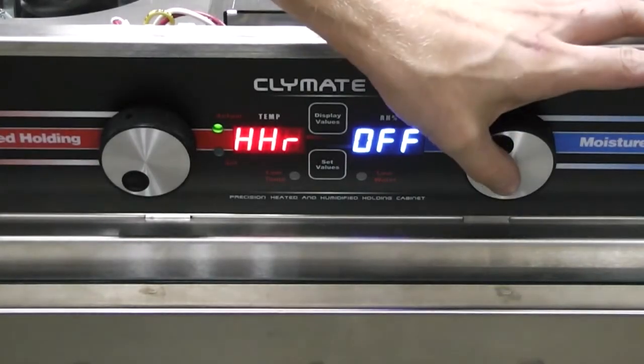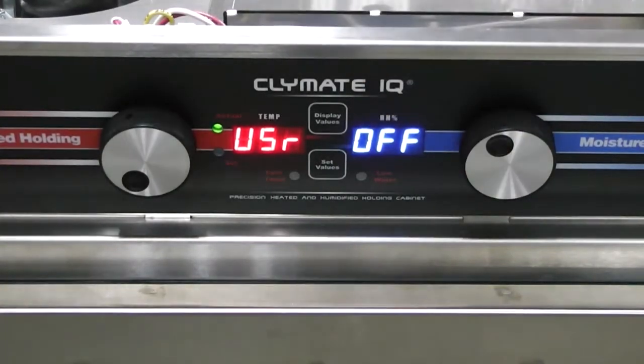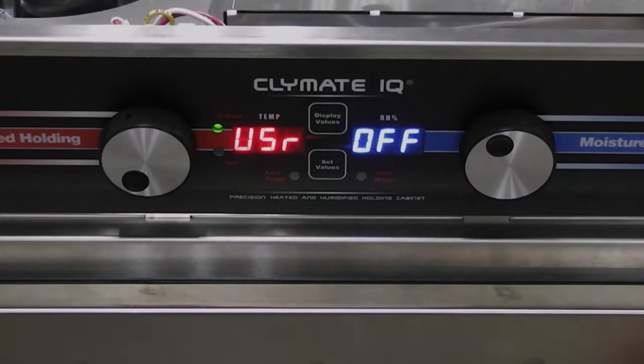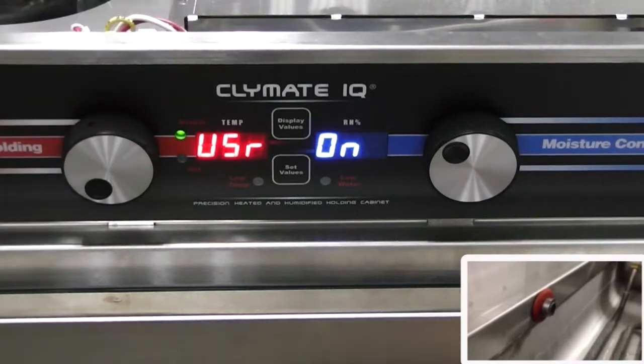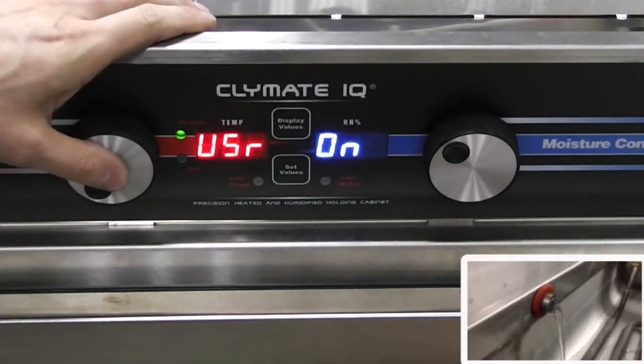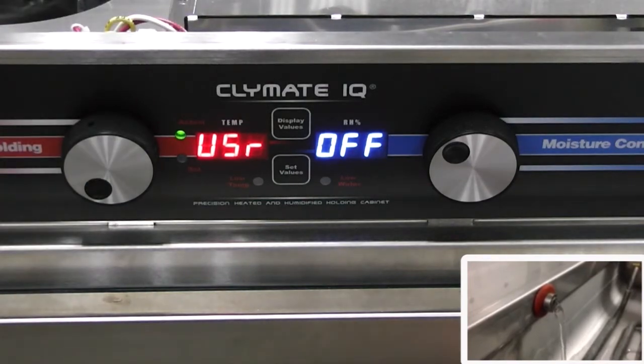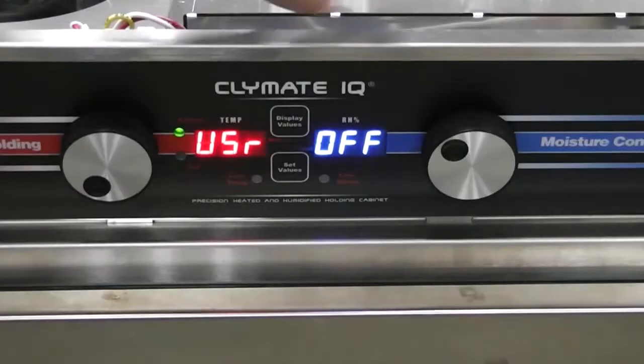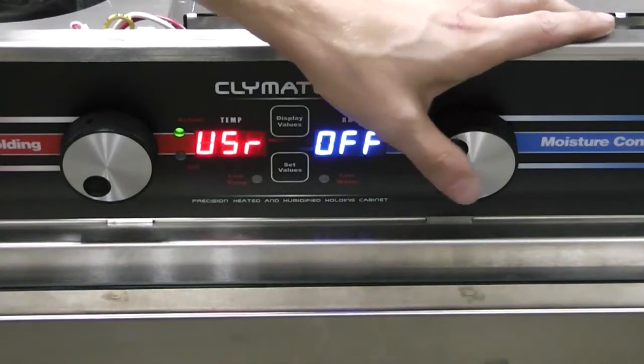Press the right encoder knob to select the next parameter, the water valve relay. Only use if the water filled option is installed. Press the left encoder knob to turn USR on and confirm that the water turns on and all the way off. Press the right encoder knob to select the next parameter, the single float switch relay.